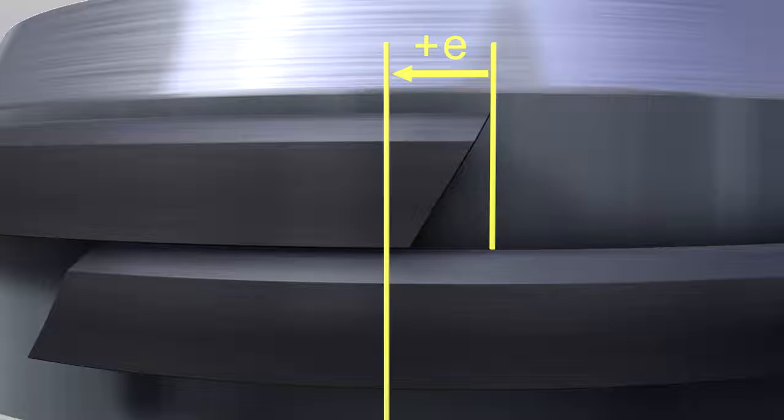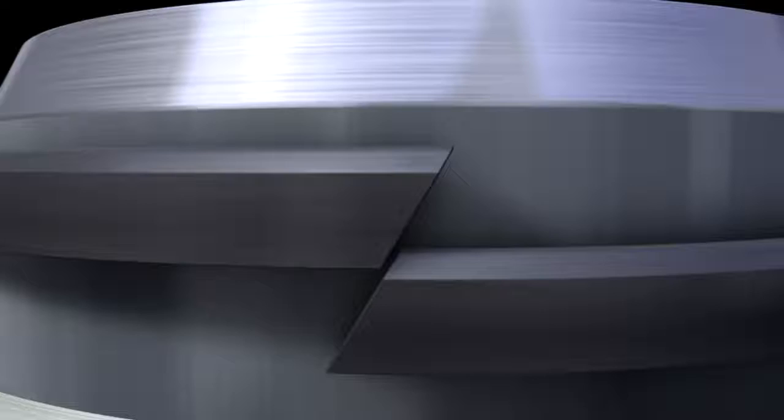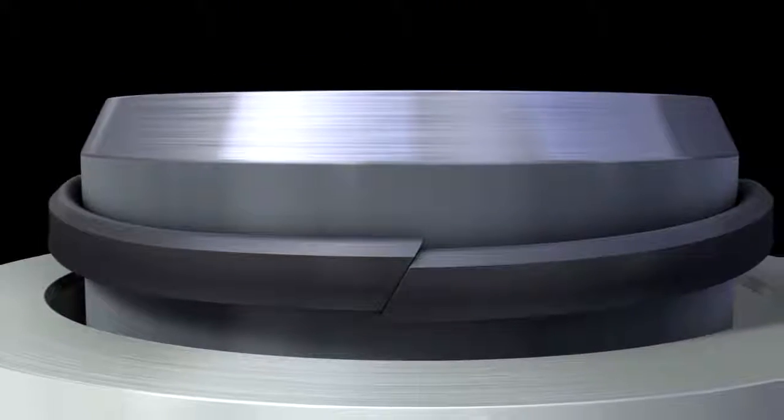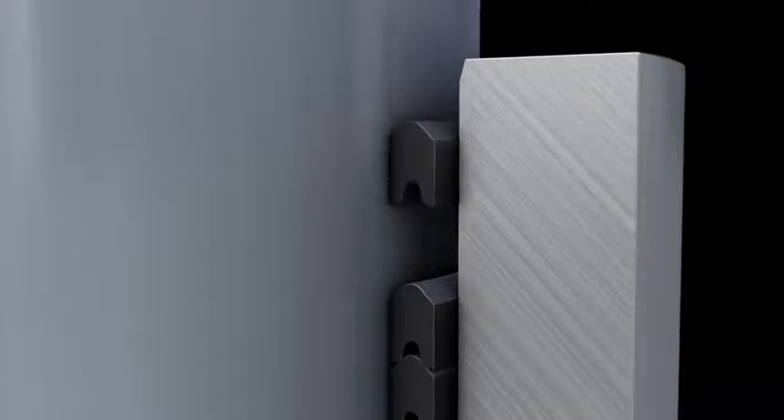Now draw an additional line from the starting point of the line at the lower end of the ring at an angle of 60 degrees. Please take care when cutting that the cut edges exhibit gap-free mating while taking the bending radius of the installed position into account. Repeat this procedure with the remaining V-rings.